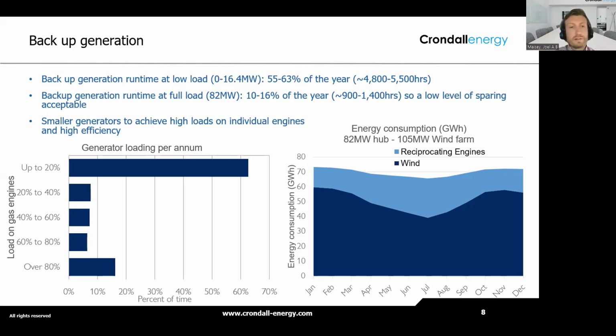The second point from that graph is that we're only running at full load, so over 80%, for around 10 to 16% of the year. So what that means is we can accept a lower level of sparing than we typically see on facilities currently. Currently it's around 2 out of 3 engines or 3 out of 4. We might be able to accept less, which helps reduce CapEx and OpEx.